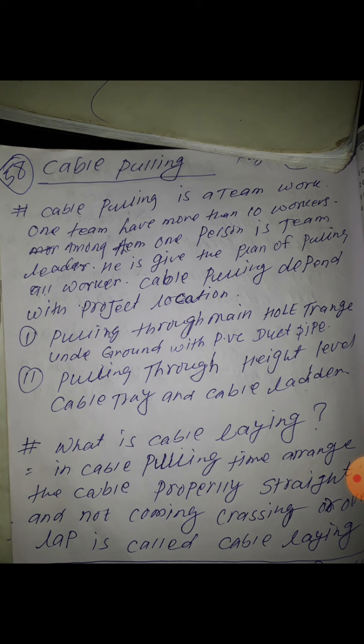If we are pulling heavy cable, armored cable, big size cables in the cable tray and cable ladder, once a twist and crossing occurs, it's not possible to remove it. So during pulling time you must be clear about this - don't make an overlap, don't make a crossing, and don't do like that - pull it straight.